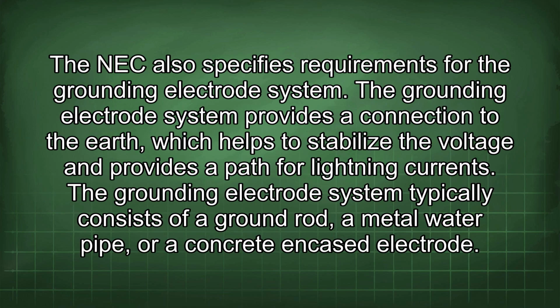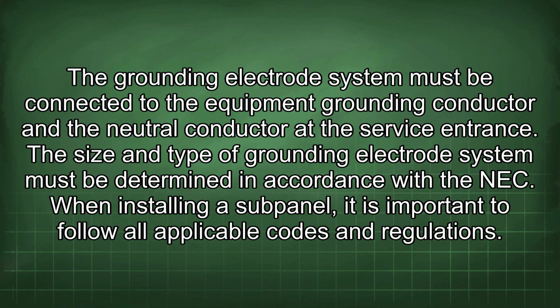conductor. The NEC also specifies requirements for the grounding electrode system. The grounding electrode system provides a connection to the earth, which helps to stabilize the voltage and provides a path for lightning currents. The grounding electrode system typically consists of a ground rod, a metal water pipe, or a concrete encased electrode. The grounding electrode system must be connected to the equipment grounding conductor and the neutral conductor at the service entrance. The size and type of grounding electrode system must be determined in accordance with the NEC.